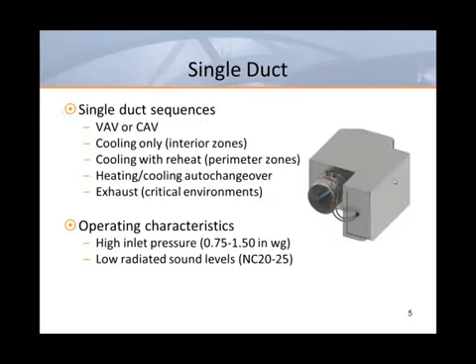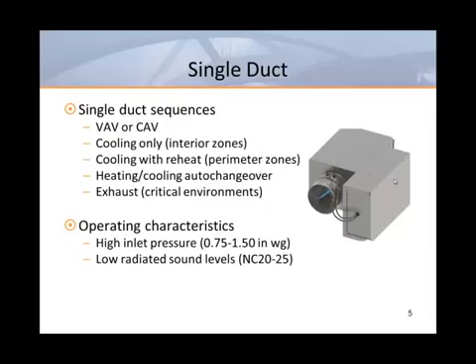The most basic terminal unit is the single duct, commonly referred to as a VAV box or shutoff box. It typically receives its supply air from a VAV air handler. A variable frequency drive controls the air handler to maintain a static pressure measured two-thirds or three-quarters of the way down the longest duct run. Single ducts can provide either variable volume or constant air volume depending on the way the flow limits have been set at the box controller.